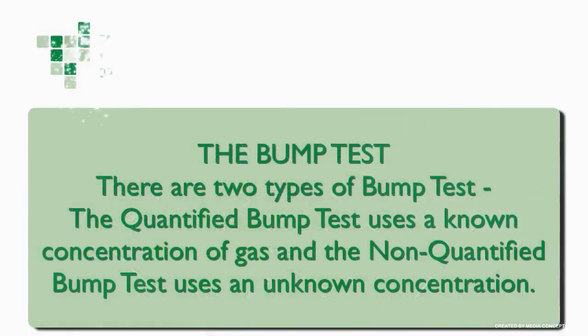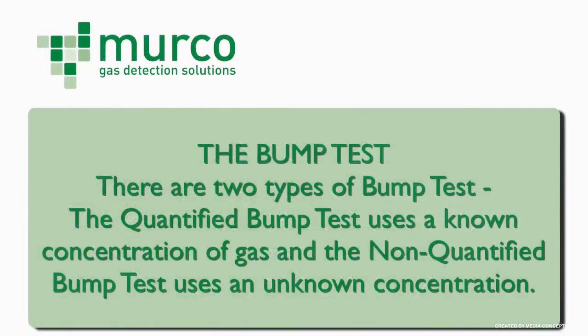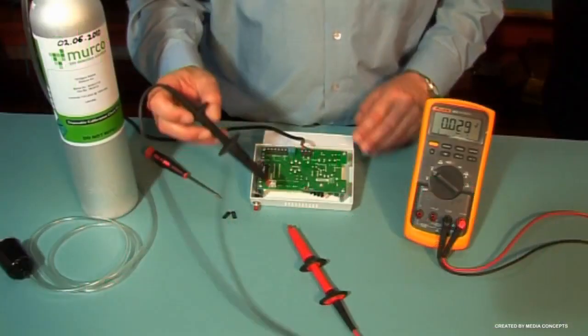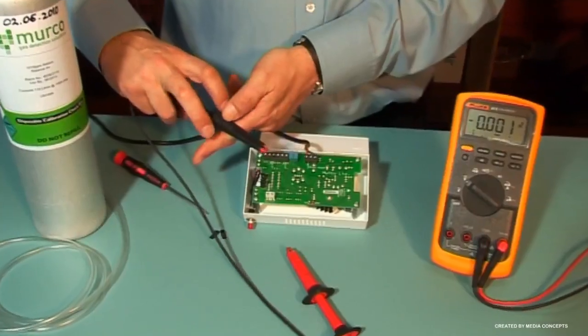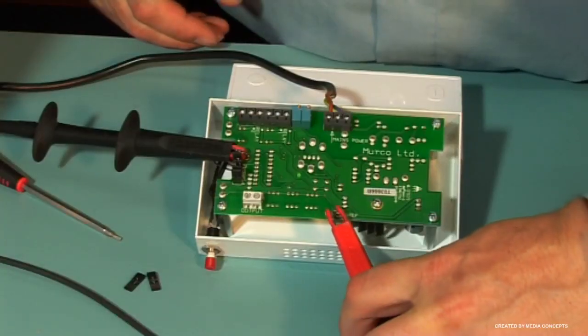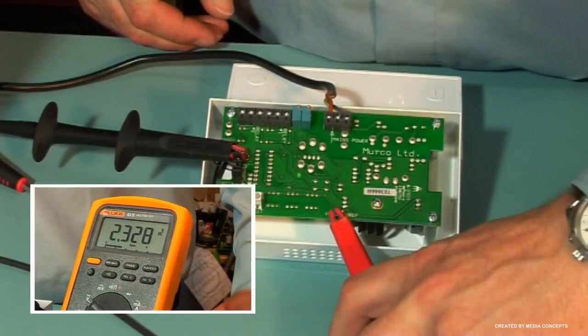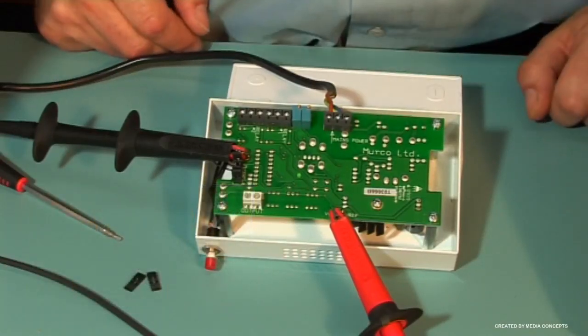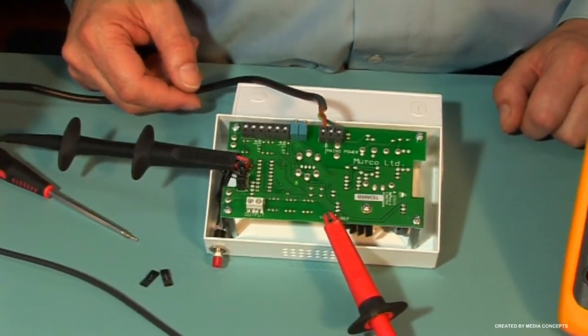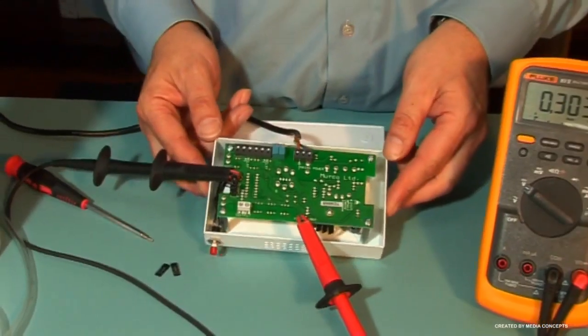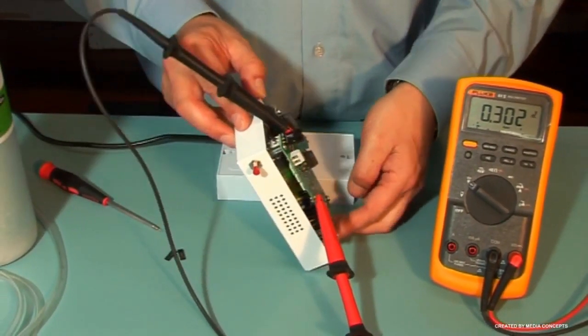There are 2 types of bump test. The quantified bump test uses a known concentration of gas and the non-quantified bump test uses an unknown concentration. Connect the voltmeter between V0 and Vs. Once the sensor starts to see gas, this voltage should increase. For a quantified test, you need to use a calibration cylinder for the target gas at the concentration as on the rating label or higher.